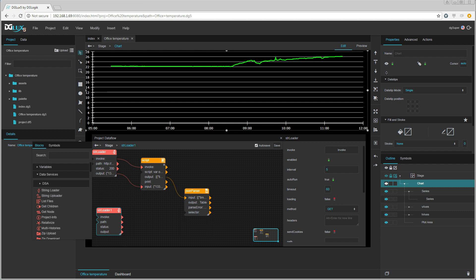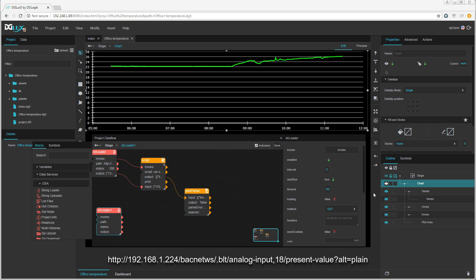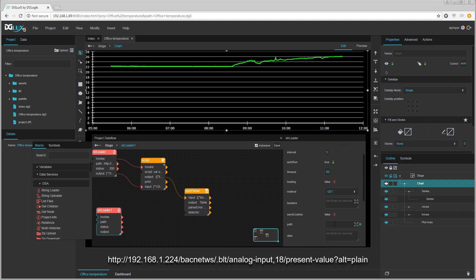I am going to let the string loader load the value every 5 seconds. And here is the path within the BACnet web services. The path points to the present value of the analog input and I want the value formatted as plain text.